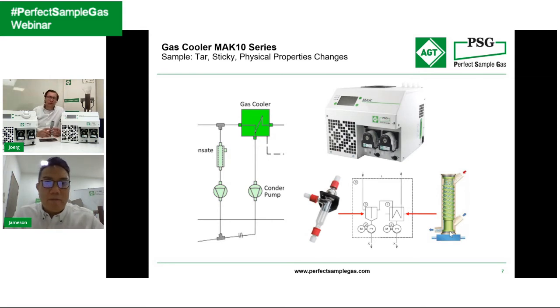It acts as a pre-separator, removing water especially when you have a high amount of it. This can really help your layout. The problem is, how do you know? Sometimes we get feedback that when you choose the wrong gas cooler, you might still overrun or overflow it, and end up with water left over, which causes big problems later in the analyzer system or the analyzer itself.